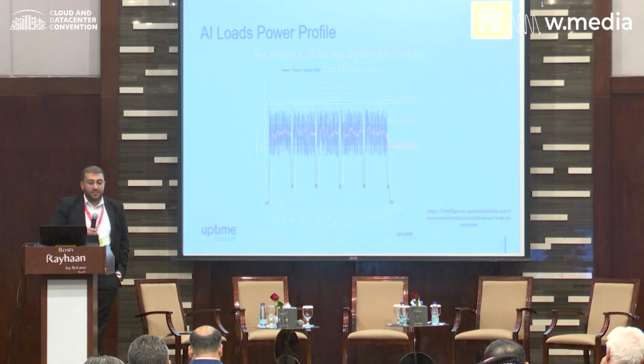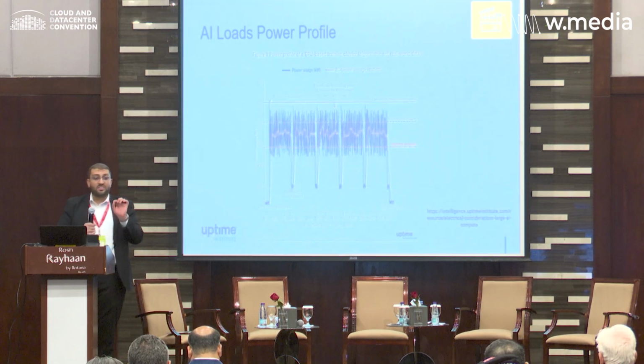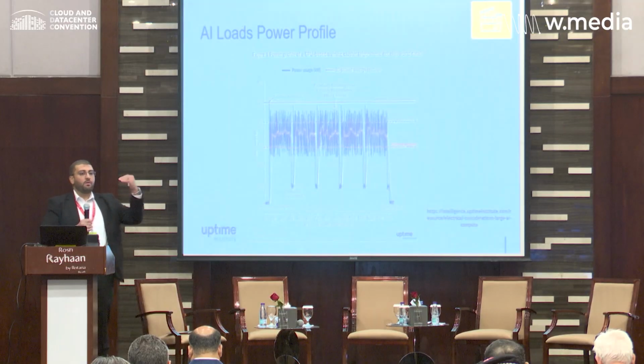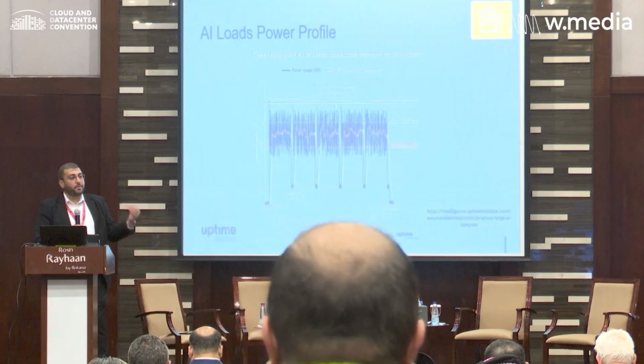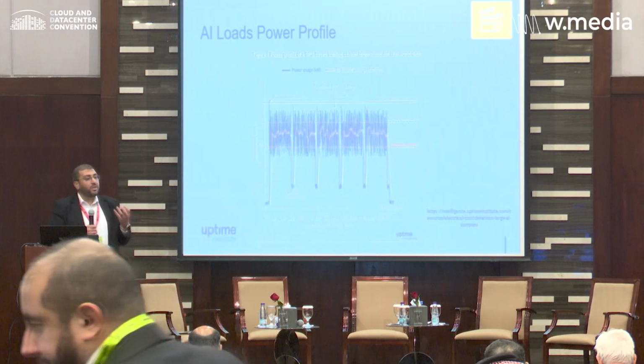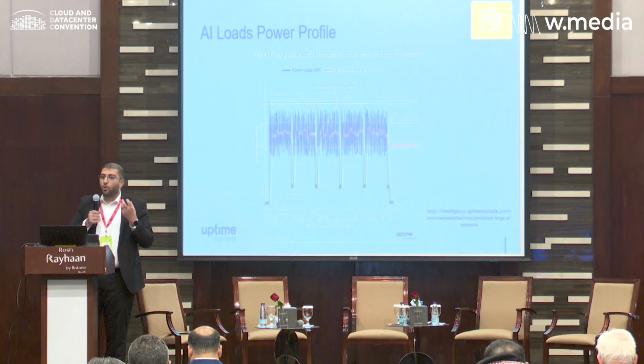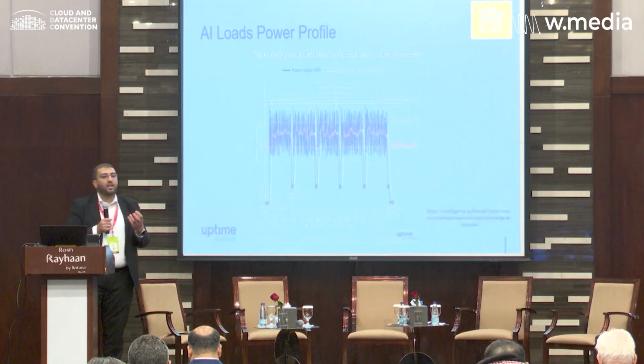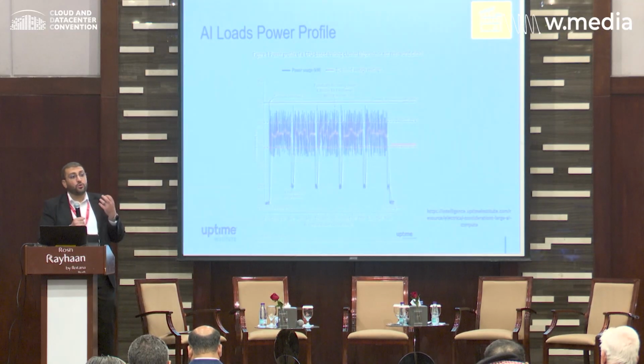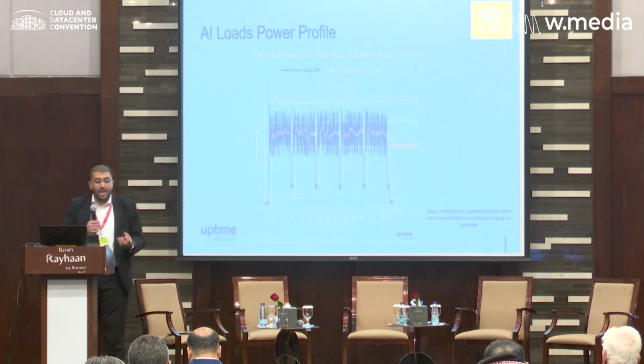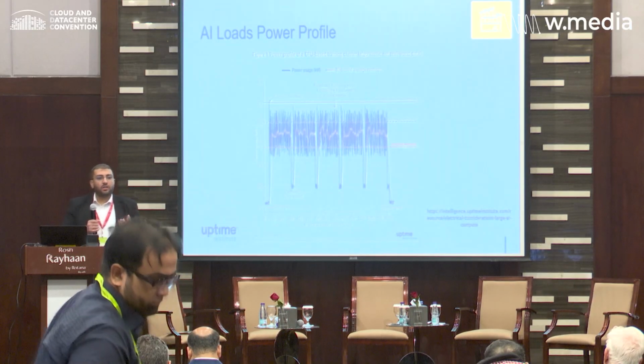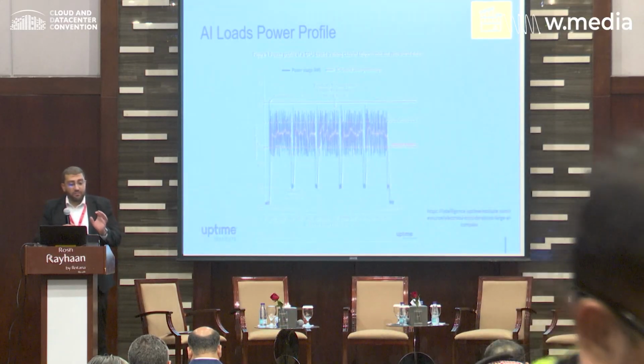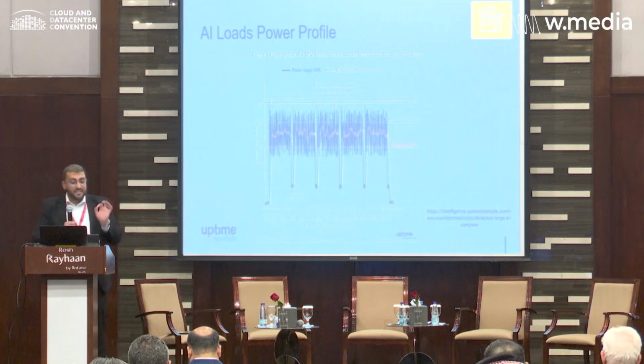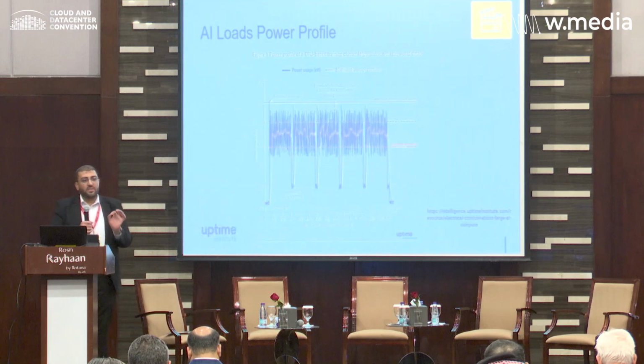During the final facility testing, the AI workload study transient, from 30% to 100%, needs to be simulated with the use of special load banks to make sure you've tested your critical capacity components, your UPSs, and your engine generators, that they are able and capable to handle this AI workload.